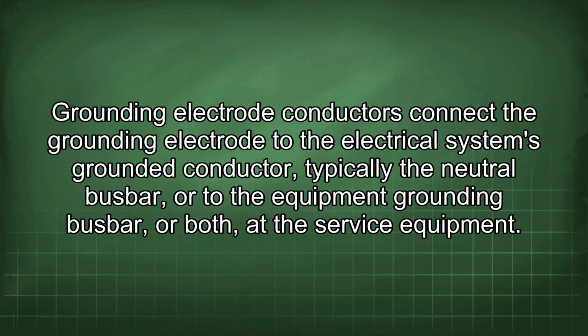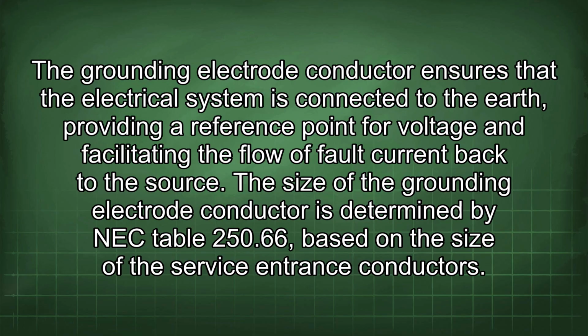Grounding electrode conductors connect the grounding electrode to the electrical system's grounded conductor, typically the neutral bus bar, or to the equipment grounding bus bar, or both, at the service equipment. The grounding electrode conductor ensures that the electrical system is connected to the earth, providing a reference point for voltage and facilitating the flow of fault current back to the source. The size of the grounding electrode conductor is determined by NEC Table 250.66 based on the size of the service entrance conductors.